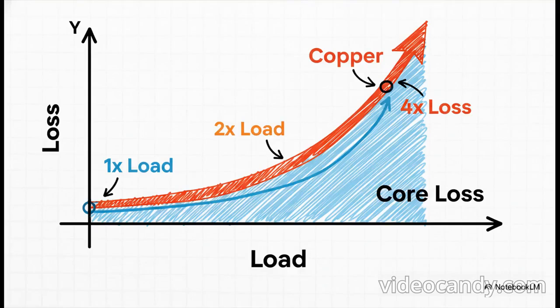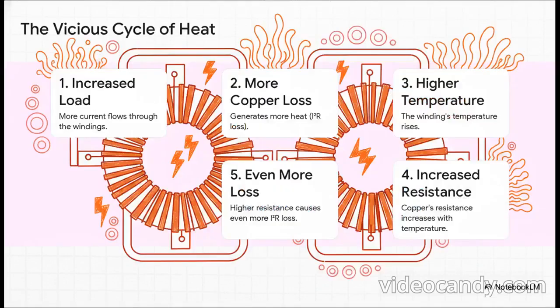This is where it gets really wild. Look at what happens as the load on a transformer increases. That flat line at the bottom is our constant core loss, just humming along, no big deal. But look at the curving line for copper loss. It doesn't just go up, it launches skyward. Doubling the work you ask a transformer to do doesn't just double the energy loss, it can actually quadruple it. That is a huge penalty for pushing it too hard.